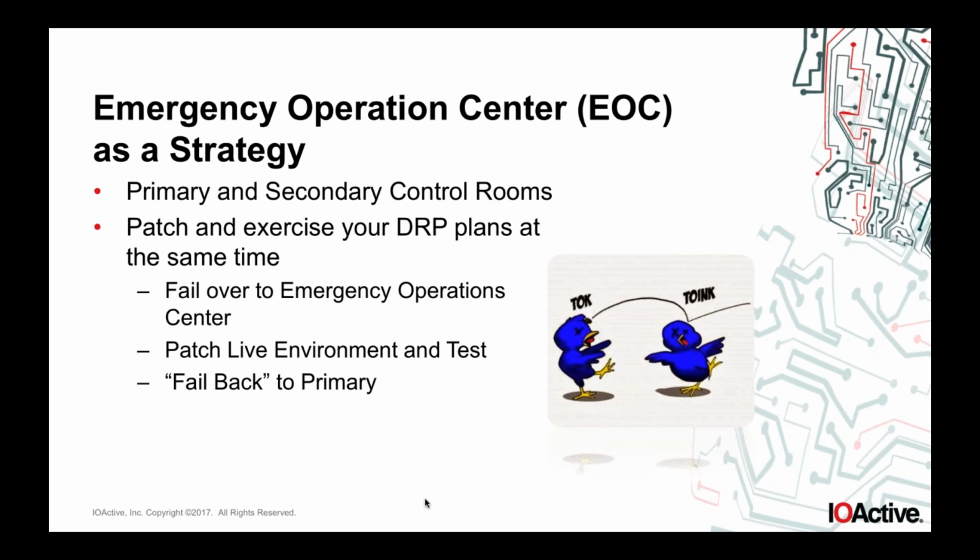So this only makes sense if you have a network that can support it, right? If you have a network that can support it, absolutely. You and I have both seen this: how many times we've been to a site that has a standby that they haven't tested, haven't communicated with, and it's not patched. Then you find out they have more problems failing over to the secondary, and I'm like, okay, that's all well and good, but it sure is good if we test this under a controlled condition, rather than when a major winter storm knocks out half your communications, right?